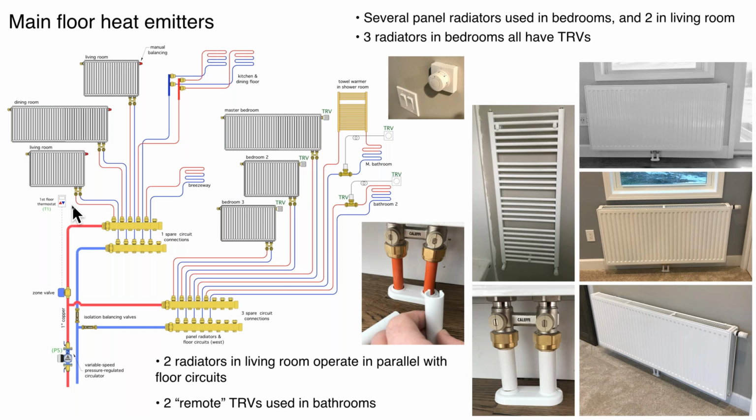If the concern is about temperature degradation, as we're seeing here in John's drawings, we're using PEX to supply our high temperature radiators, which is a great idea. And all the PEX tubing that's for sale in North America should be certified to the CSA standard called B137.5. That's B as in Bob, 137.5. And that standard requires long-term testing on the PEX tubing before it's certified and allowed for sale. And the tubing is all rated for continuous operation of 100 PSI at 180 degrees. So I'm pretty sure the John system is not running at 100 PSI, even though it might be at 180 degrees.